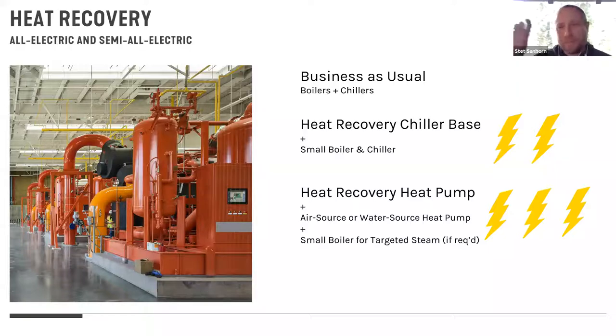But we talk about moving from that, at least getting to a heat recovery chiller base. We're trying to cover the majority of your load through heat recovery chillers with auxiliary boiler or a traditional chiller as needed to cover those peaks and valleys that don't get covered within your simultaneous heating and cooling band.